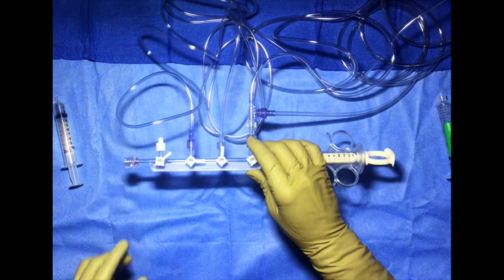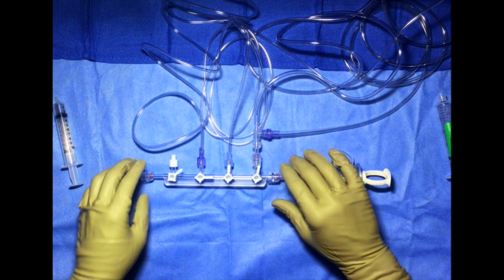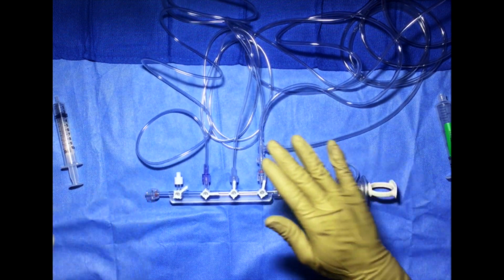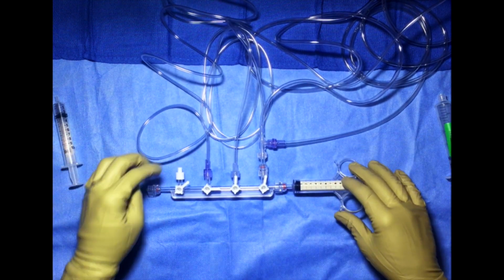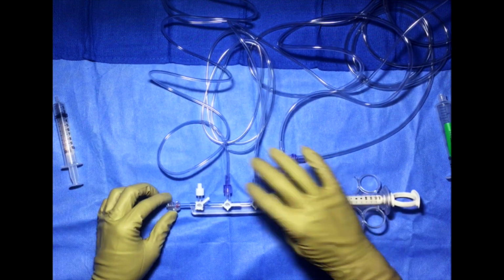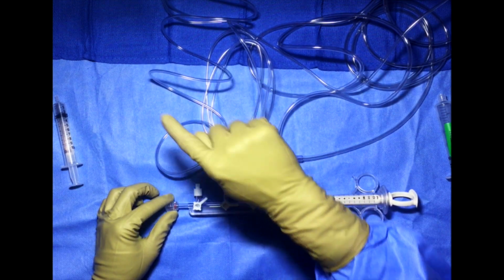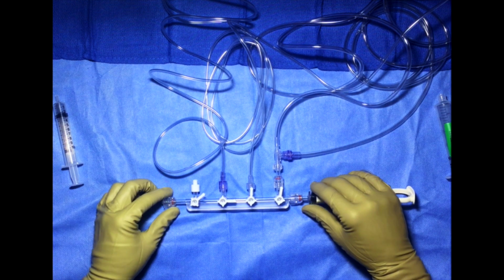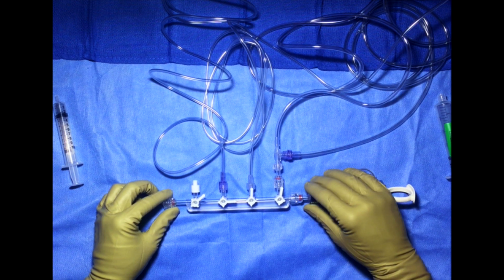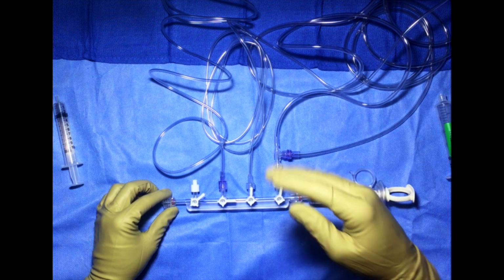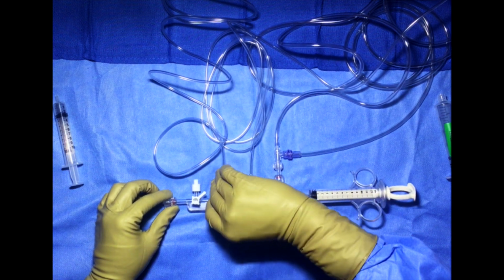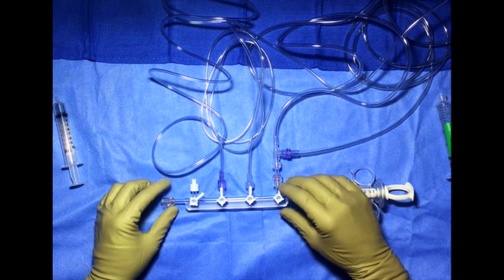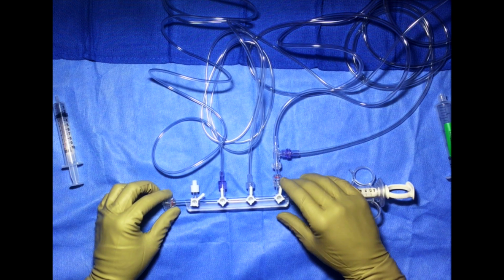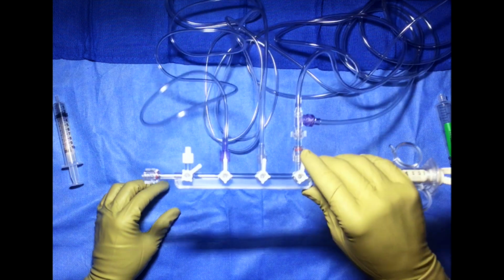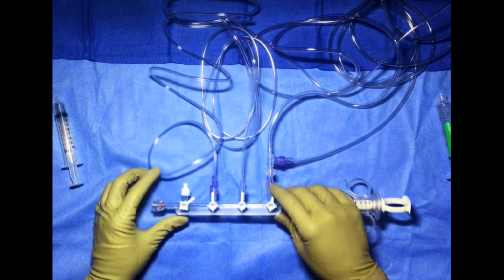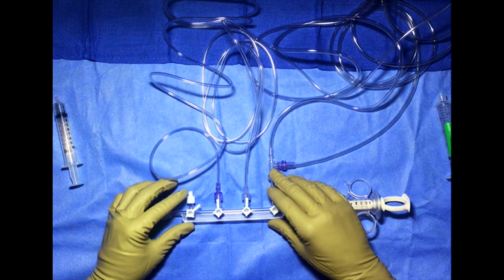But it's probably going to be somewhere in that valley of the patient's legs, just because of how people's bodies are built. But you'll figure out how to kind of do that. You could have this go off the table and do pole mount off the table transducer. You would just flush to the other person over there who would be clearing it out, who might set everything else up. The one good thing about those transducers is once you zero them, it does not matter what I do here, up, down, it's zeroed over there, and that's not moving.